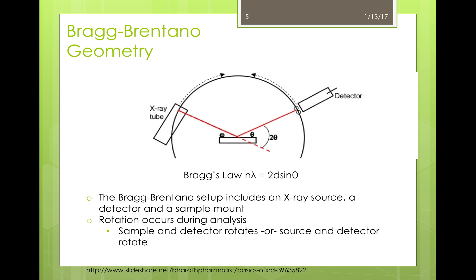However, the rotation of the source and the detector is very demanding on the machine, which is why some machines have a rotating sample plate. The angle that forms between the source of the X-rays and the sample on the XRD machine is omega, and the angle between the detector and the incident beam from the X-ray source is consistently at 2-theta, meaning that it's always double the omega angle.